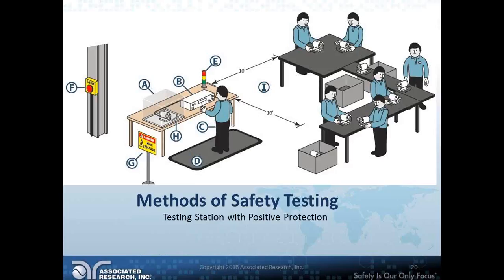Some extra methods you can see here: one labeled D is an insulation mat that the operator is standing on that isolates him from ground potential. You'll notice a G, that's a high voltage sign, letting anybody outside the station know, hey, don't come in here unless you're trained because we have high voltage testing going on. F is an E-stop going into the whole station, so should somebody outside see a problem, they can hit that E-stop without going into the hazardous area and shut everything down.